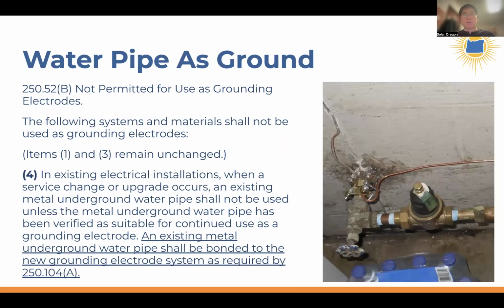Now, this provision about using a water pipe as a ground: in the past, water pipes were made of metal. Modern pipes are mostly plastic now. Back when there were no plastic pipes, using a water pipe as a ground wasn't the worst idea. But now, with more pipes being plastic, if you have a water pipe problem, the chance your plumber switches to plastic pipe is nearly 100%. So the Oregon Electric Code says that if your existing system uses a water pipe as ground, you need to first verify it's actually grounded, not just connected to the metal portion, since further out it turns to plastic in the dirt.